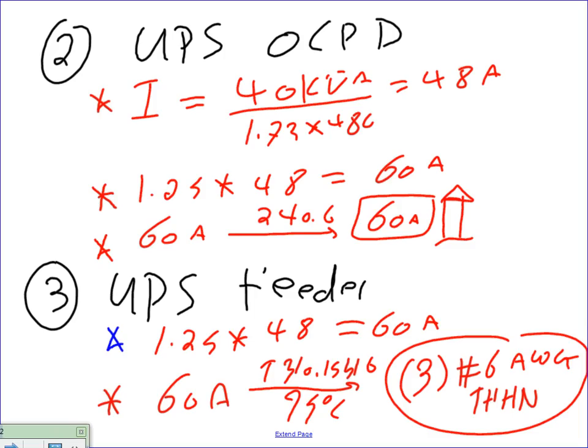You bring just 3 phases to the UPS because you create your own neutral later on. It's like the transformer for the receptacles. We don't bring a neutral to feed the transformer that feed receptacle. We create our own neutral. Okay, so I can almost say match overcurrent device, right? Almost. But we're sizing based on continuous load. Any question, guys, about the primary? This is the UPS overcurrent device and the UPS feeder.